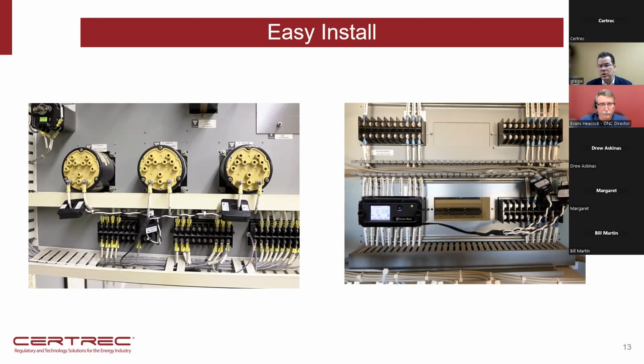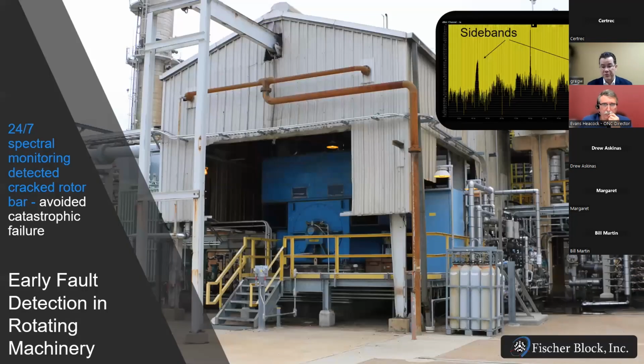And yeah, we'll communicate typically through Ethernet. That device there, I don't see an Ethernet cable. However, we have an Ethernet jack in our device. Each one of our devices has an IP address. So it's communicating, traditional TCP/IP to a server, which can be in the substation, running WaveIQ behind the enterprise firewall, or the server can be remote, still behind the customer's firewall, but at a remote location. So you don't require any type of a server in the substation, or it can actually route to any server outside the network, which could be Fischer Block servers for some of our customers, with servers in-house that we have, and we also have a cloud platform running on AWS. And then through the Certrec portal as well.